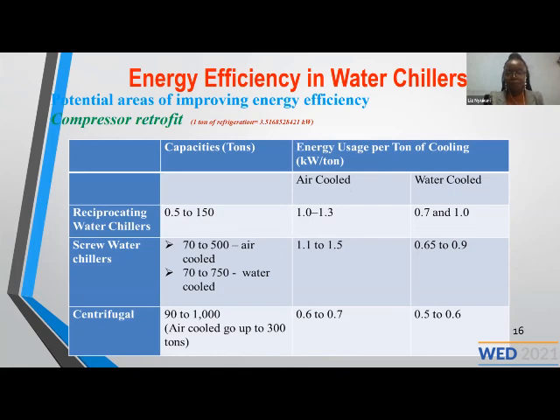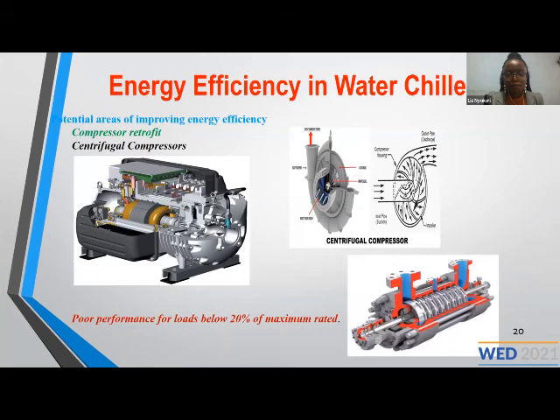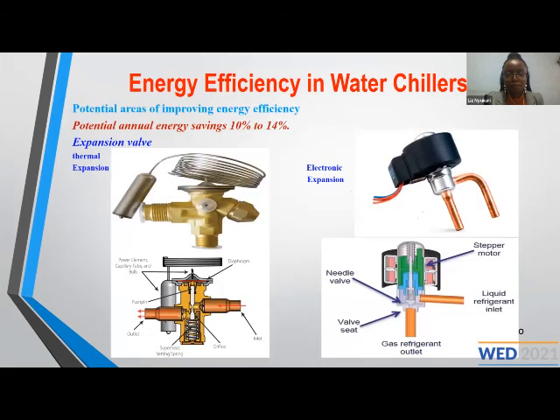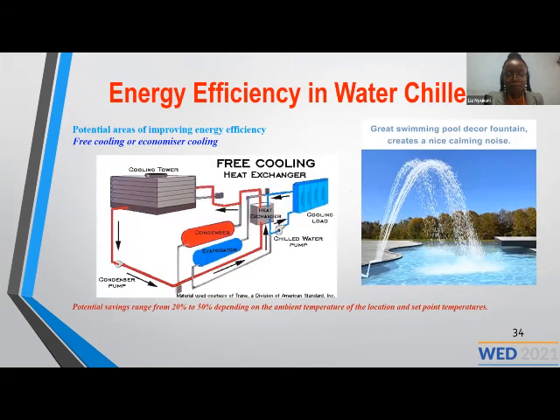So it's not something you can just sit down and decide that the cooling tower is high, you just switch off. That's why I've also seen there is a training which should be done on the design of the cooling towers, so that you can understand how they operate. But all in all, you need a very good control system for your water chillers. With good control systems, you can achieve up to 20 to 50% of the energy savings.